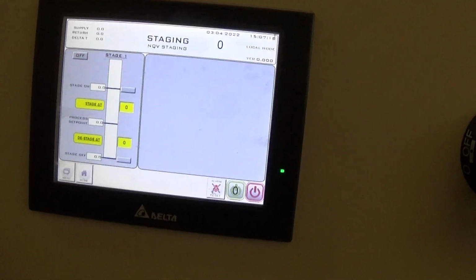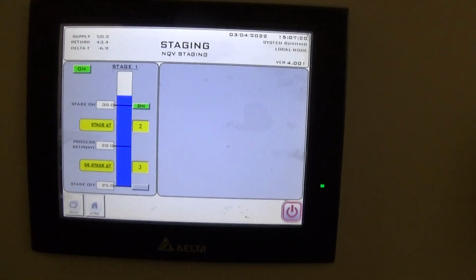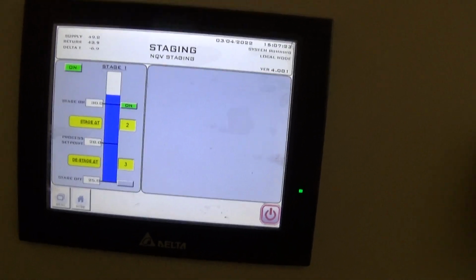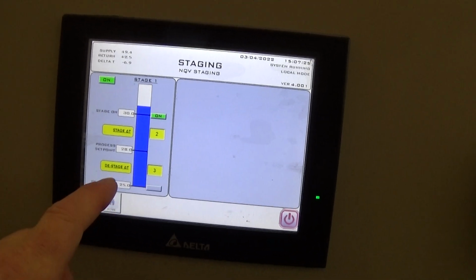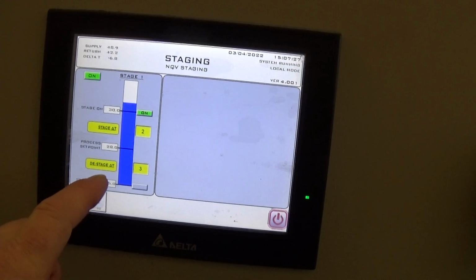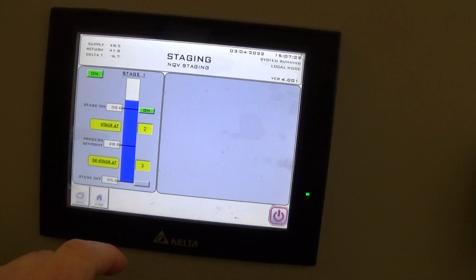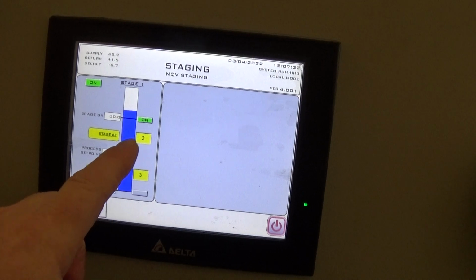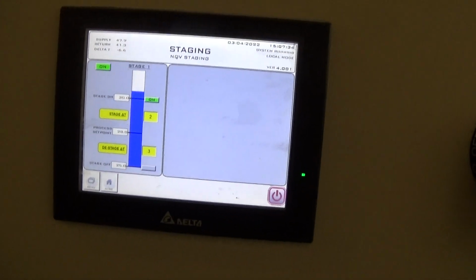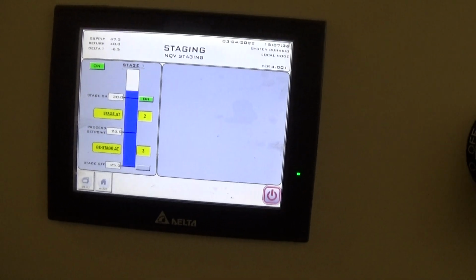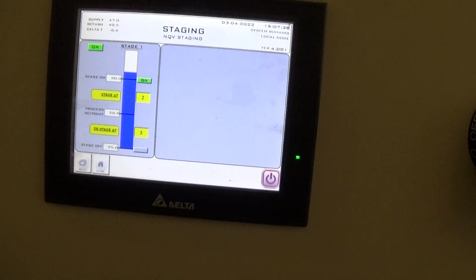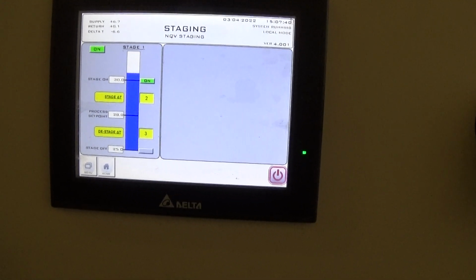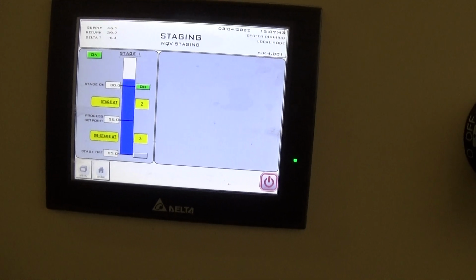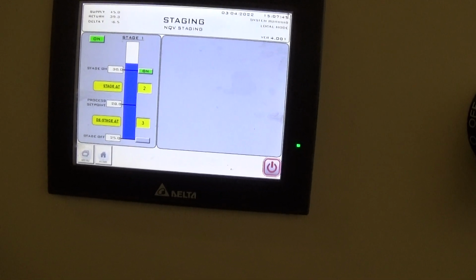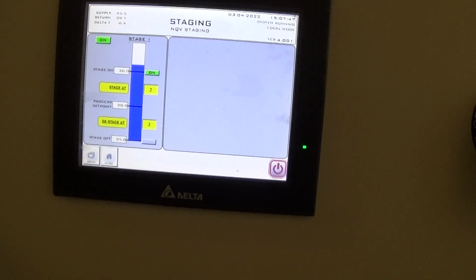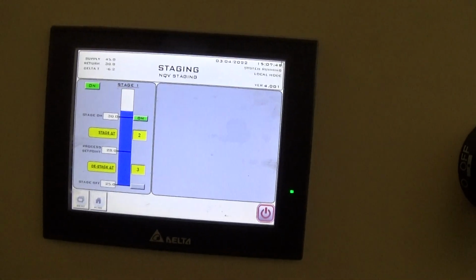Compressor staging. That's actually showing you when we kick in and kick off. We currently have 3 degrees below set point and 2 degrees above set point for the differential. I wouldn't go much tighter than that. You can with this type of compressor, but in a brewery batch cooling environment, I don't think you're going to find that's needed. I suggest try just leaving at these settings that we have in it already.